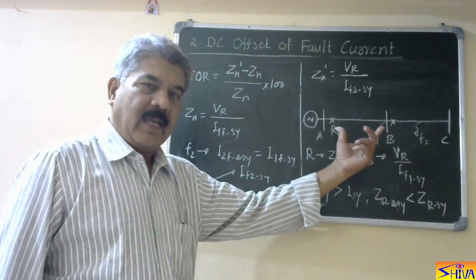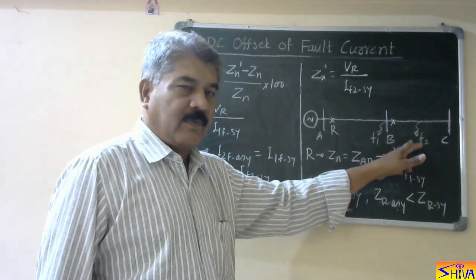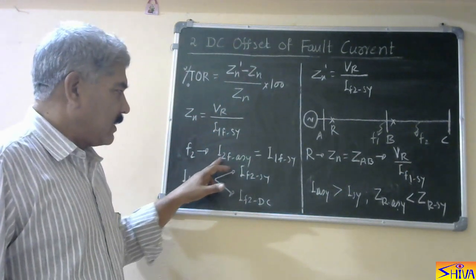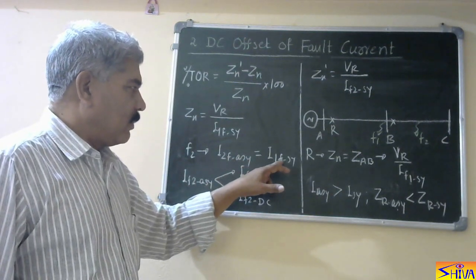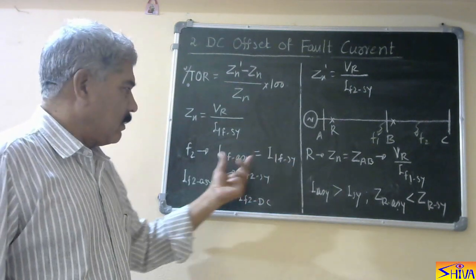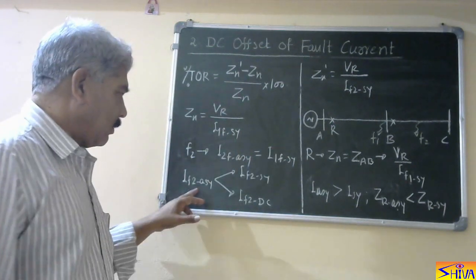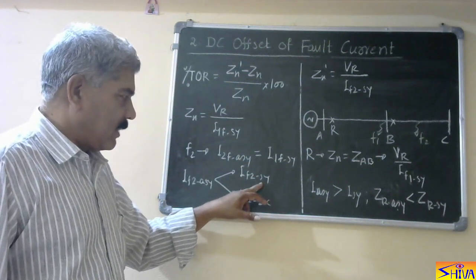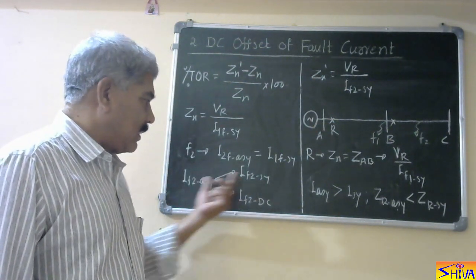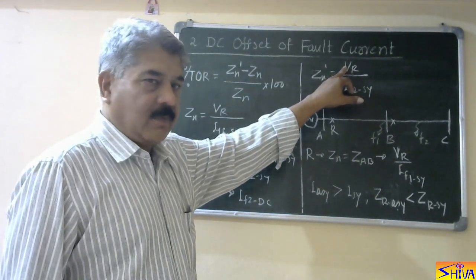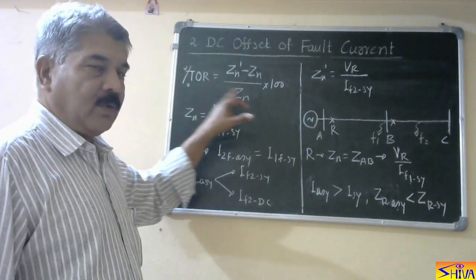This relay is protecting line section AB. Now if F2 is in section BC, in normal conditions this relay should not operate for fault F2. But F2 has an asymmetrical fault current — symmetrical component plus DC offset — and it equals the fault current at F1 with symmetrical component only. Therefore the relay operates, and we compute the transient overreach. For this, the asymmetrical fault current at F2 has two components: symmetrical component and DC component. ZN_dash is computed from the symmetrical component of the fault current at F2, and using ZN_dash and ZN we compute the percentage transient overreach.